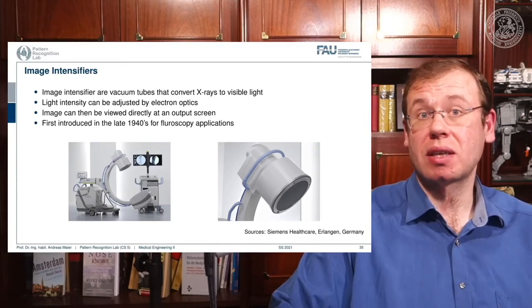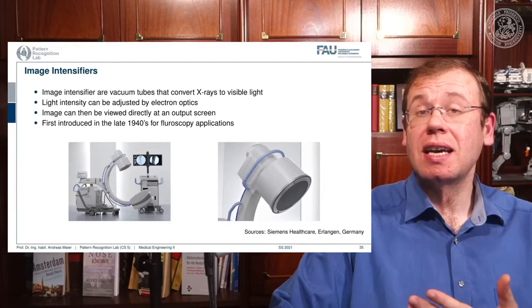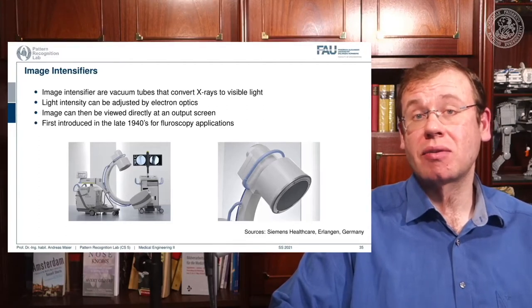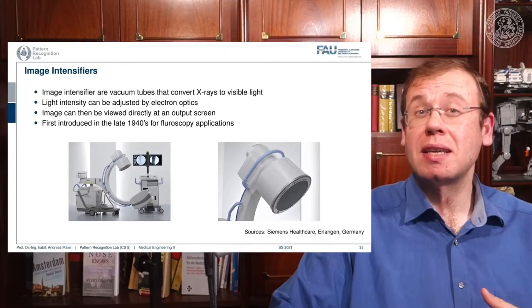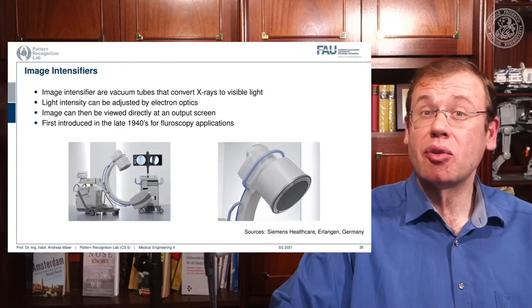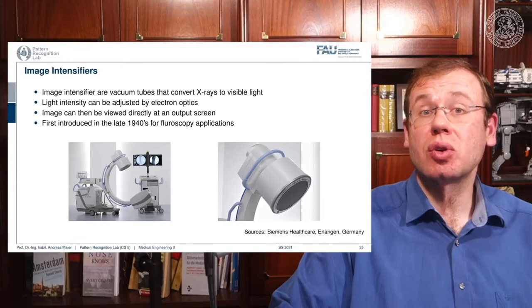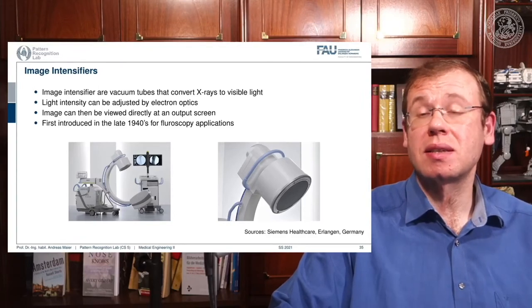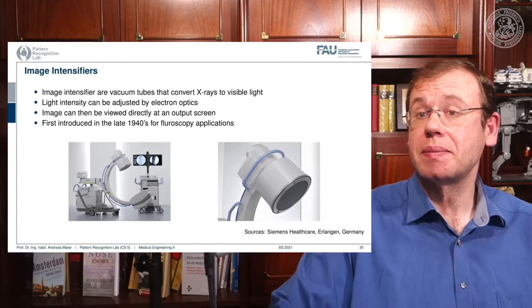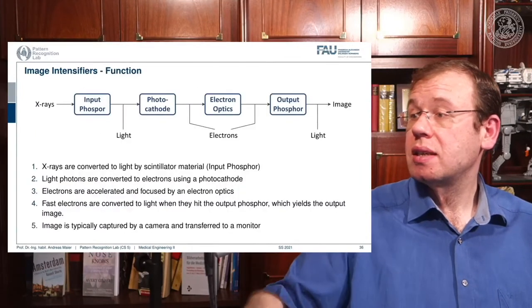There is electron optics that allows us to essentially zoom in and zoom out continuously. This is also why this technology has been very popular for a long time, because with a flat panel you can only work with different binnings. The difference is like in your camera where you have an optical zoom for continuous zooming versus a digital zoom which causes interpolation or jumps in discrete steps because you bin — you summarize a certain number of pixels.